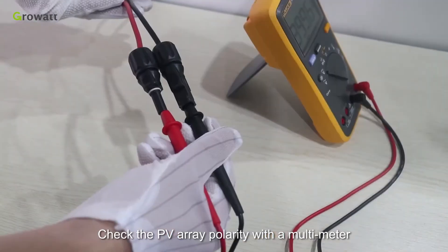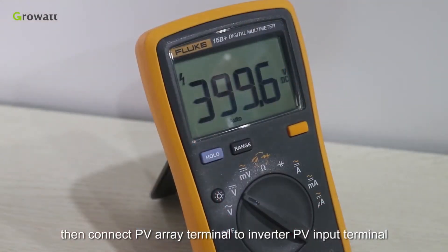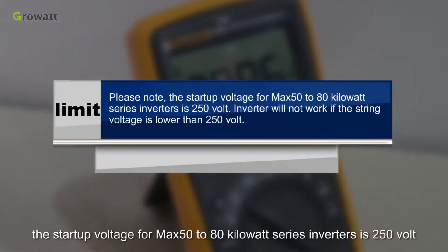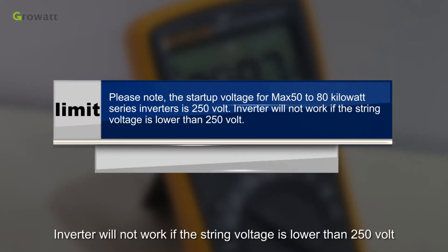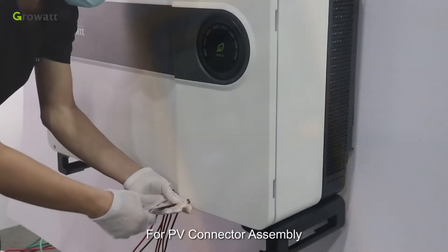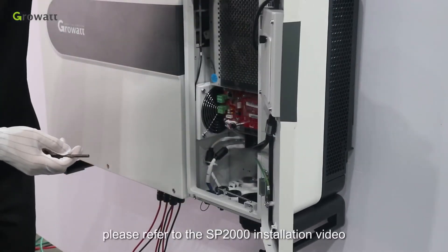Check the PV array polarity with a multimeter, then connect the PV array terminal to the inverter PV input terminal. Please note: the startup voltage for the Max 50 to 80 kW series inverters is 250 volts. The inverter will not work if the string voltage is lower than 250 volts. For PV connector assembly, please refer to the SP2000 installation video.